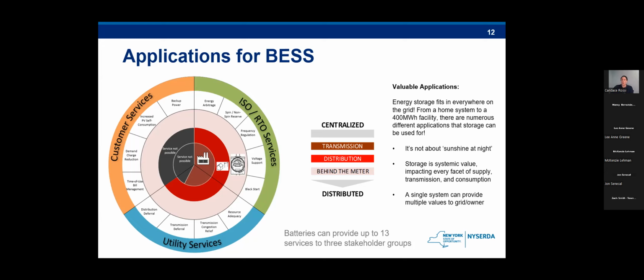It can also support transmission-level voltage support, which ensures reliable and continuous electricity flow across the power grid. And then it also aids in what's called a black start. In the event of a grid outage, black start generation assets are needed to restore operation to large power stations in order to bring the regional grid back online.